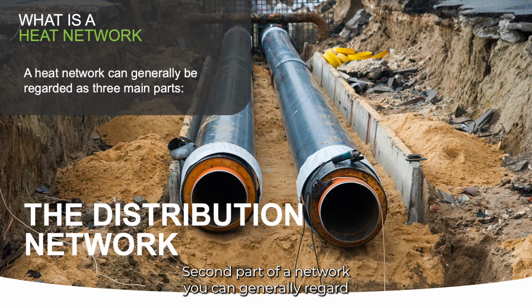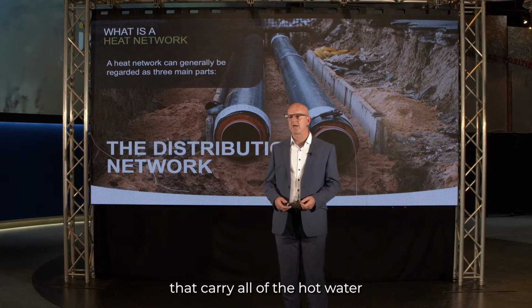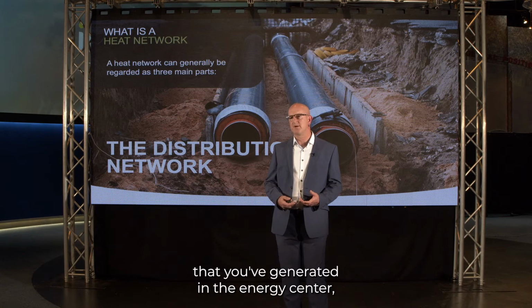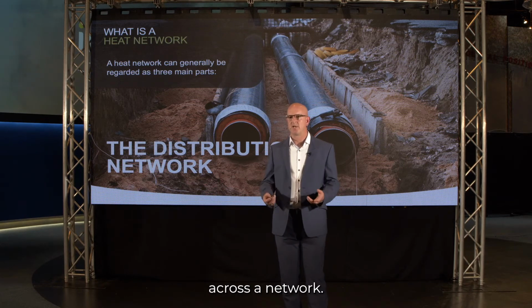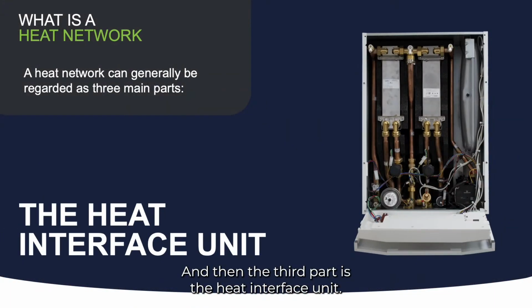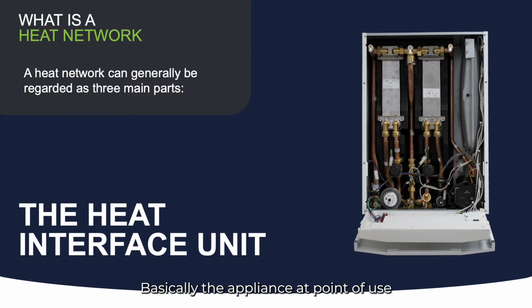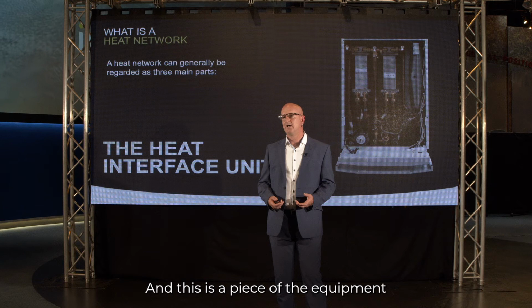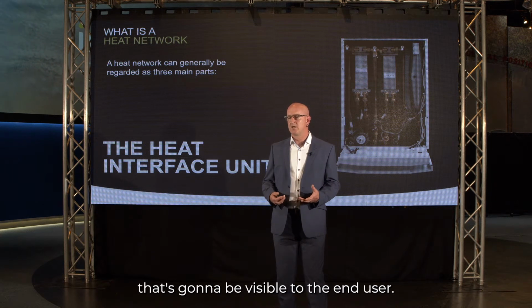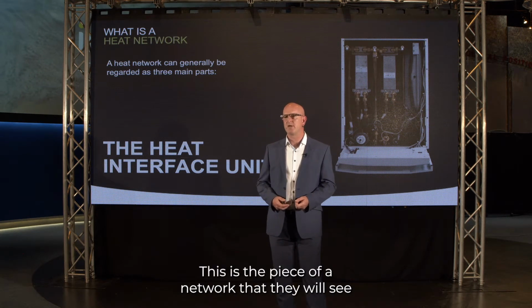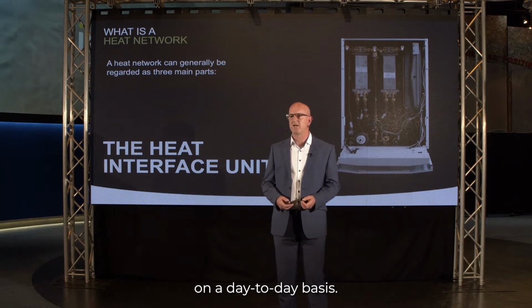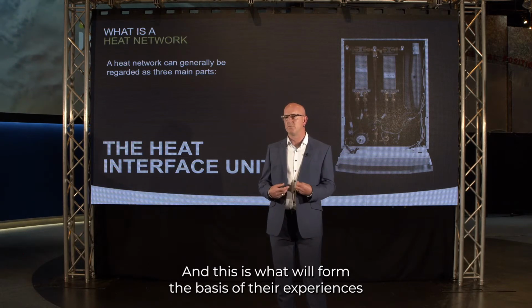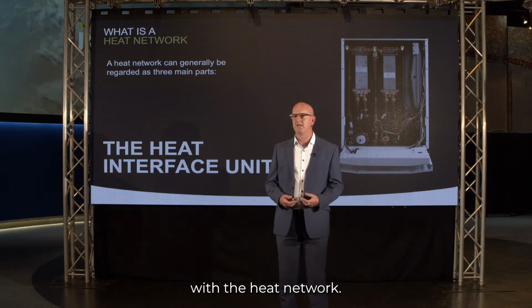The second part of a network you can generally regard as the distribution. This is generally a series of insulated pipes, typically buried underground, that carry all of the hot water that you've generated in the energy centre across a network. And then the third part is the heat interface unit, basically the appliance at point of use inside the residence or the dwelling. This is a piece of equipment that's going to be visible to the end user. This is the piece of a network that they will see on a day-to-day basis, and this is what will form the basis of their experiences with the heat network.